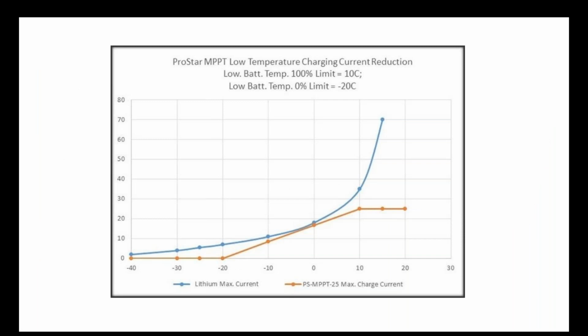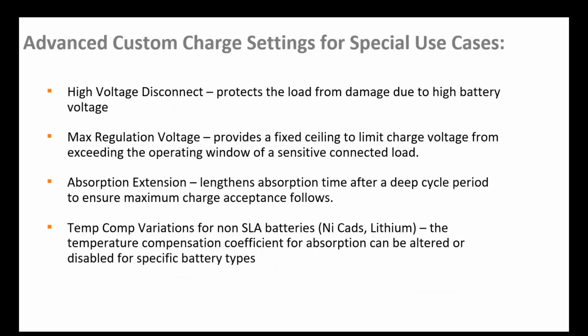This is just a graph illustrating the low temperature charge reduction feature that we spoke about earlier on the last slide. You can see how some batteries may have a characteristic curve as temperatures start to decrease, and our low temperature fold-back range, specifying the low temperature threshold and the high temperature threshold, is a good way to approximate that curve while still harvesting as much energy as you can into that battery without harming it. So that just illustrates the usefulness of that feature.